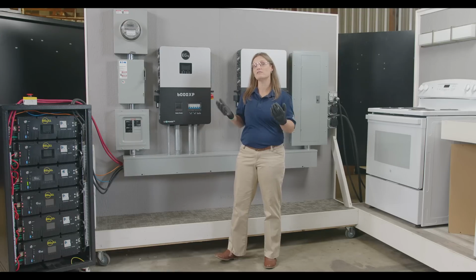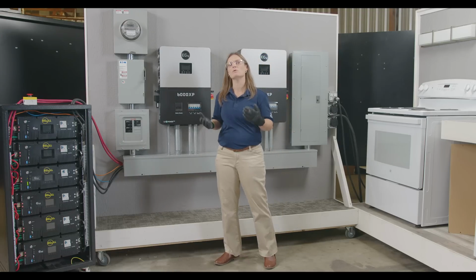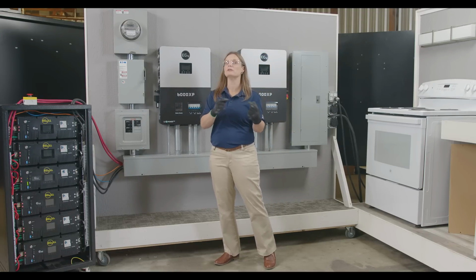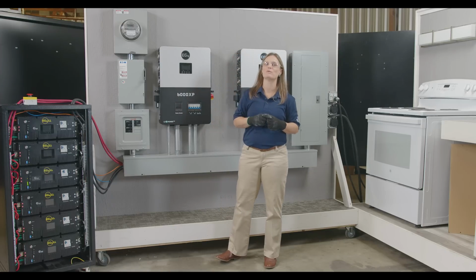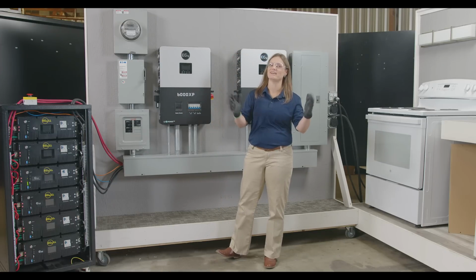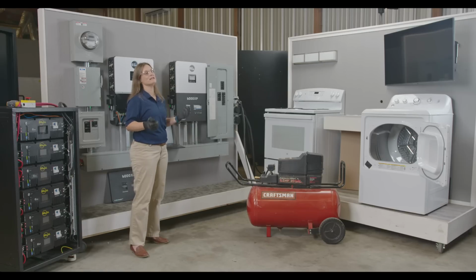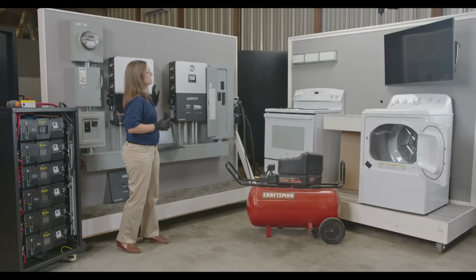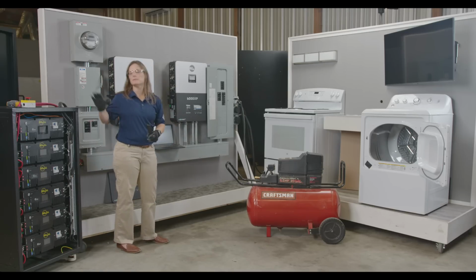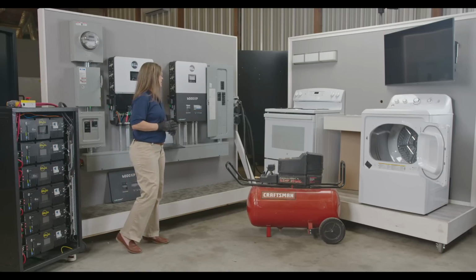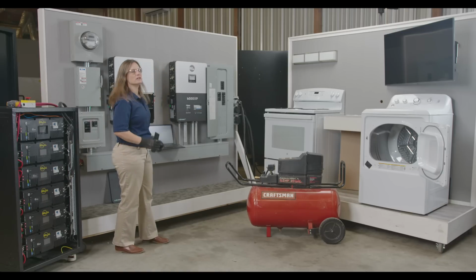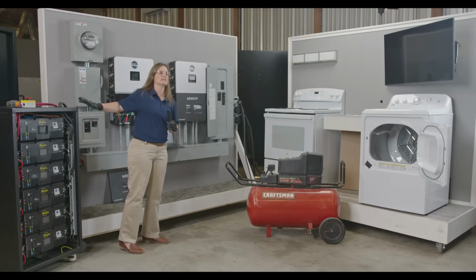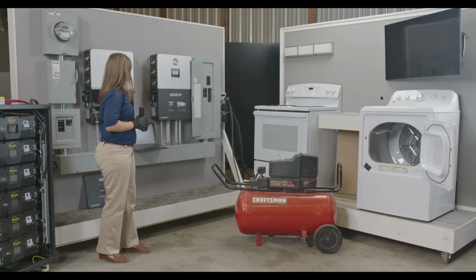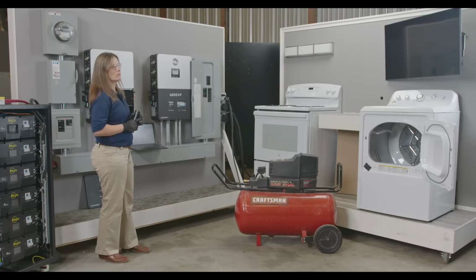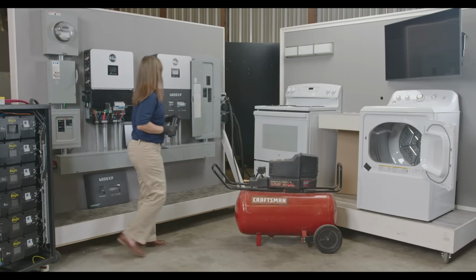Okay, friends, we've got everything set up, but how do we know this inverter can handle the loads you'll be throwing at it? Well, there's only one way to find out: a load test. All right, it's time to finally see what these two inverters can do. We've got two wired in parallel, being powered from a battery bank, and currently we are showing 42 watts. That is our less than 50 watt idle consumption connected to battery bank DC. So let's power on our loads and see what we're able to run off of these two inverters.